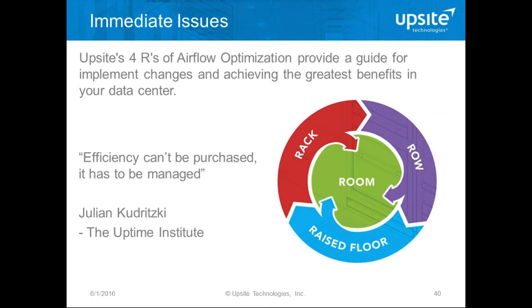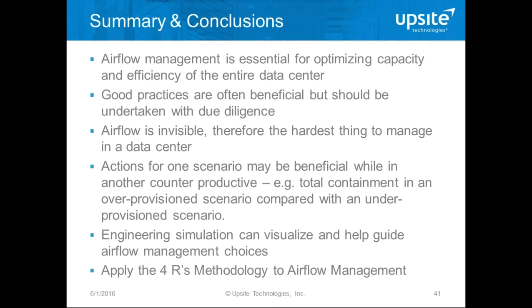Improved airflow management can also have a profound impact on the capacity of the cooling equipment — being able to install more IT equipment — particularly important for both enterprises and co-locations trying to maximize kilowatt usage in a room. The Four R's of airflow management can be a real helpful way to make sure each area is being addressed. Good practices and best practices are beneficial and a necessary step towards optimization, but each individual one does not stand on its own.